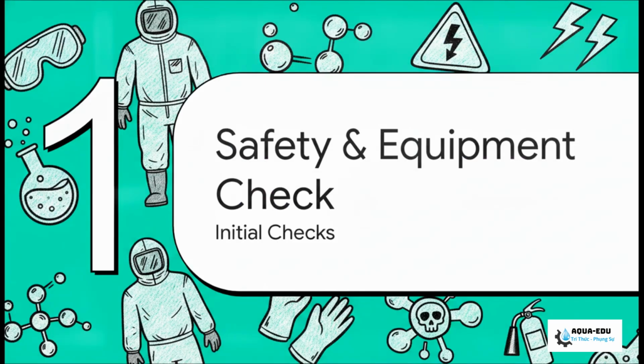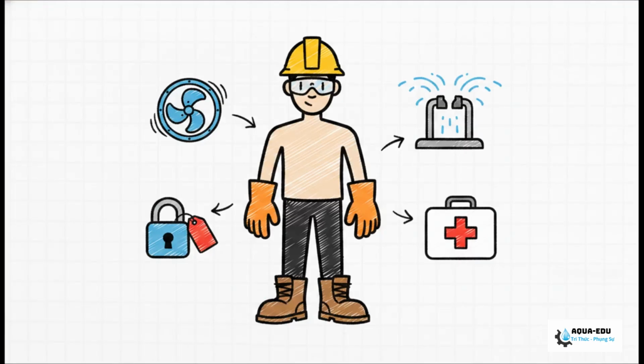Okay, let's kick things off with Section 1, Safety and Equipment Check. Before we even touch a single piece of equipment, brothers, your safety protocols have got to be locked in tight. You must be fully equipped with PPE: chemical-resistant rubber gloves, safety glasses, your hard hat, and steel-toe insulated shoes. Next, execute a strict lockout-tagout on the electrical system before making any connections, no exceptions.